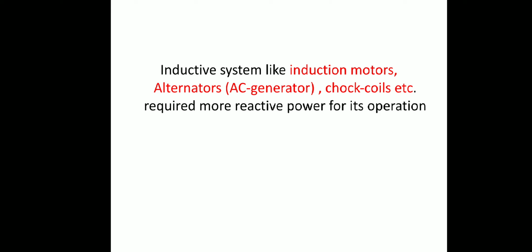Inductive systems like induction motor, alternator, also called AC generator, choke coils, etc. require more reactive power for their operation because they are inductive loads. To improve the power factor, we have options like introducing a capacitor bank to the system, or a synchronous condenser for the power system, or a phase advancer. Mainly at the LT side, capacitor banks are used for improvement of the power factor of the system.